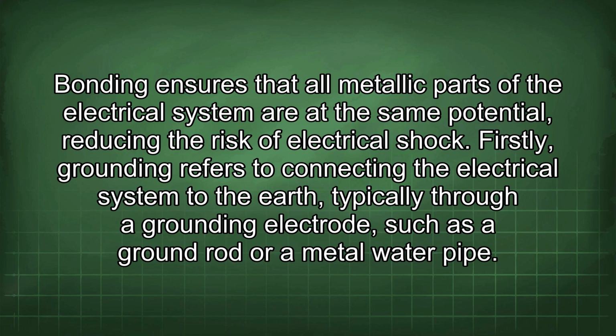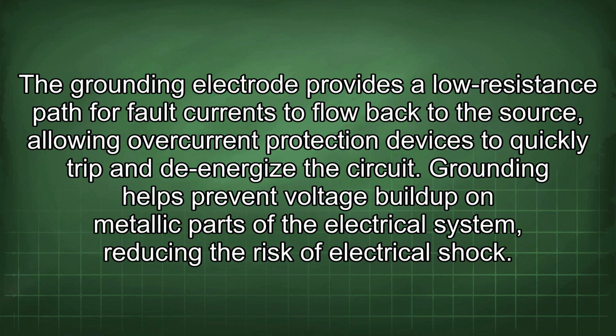Firstly, grounding refers to connecting the electrical system to the earth, typically through a grounding electrode, such as a ground rod or a metal water pipe. The grounding electrode provides a low resistance path for fault currents to flow back to the source, allowing overcurrent protection devices to quickly trip and de-energize the circuit. Grounding helps prevent voltage buildup on metallic parts of the electrical system, reducing the risk of electrical shock.